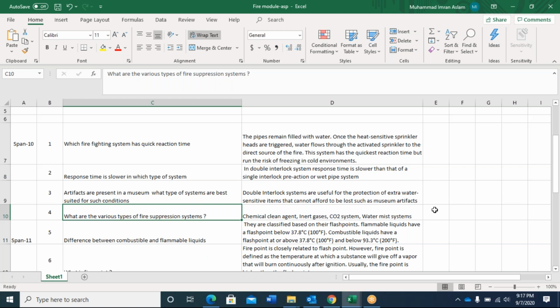Actually, what happens is water will be there up to the deluge valve, and the rest of the pipe will be filled with air. I will not be talking about the deluge system, only the pre-action system. We call it a deluge valve, so up to that valve water is there, and the rest of the pipe is filled with air. We call it a dry pipe system. In this, we have this interlock system, which comes under pre-action systems. So you are saying that the deluge system and the pre-action system are the same?